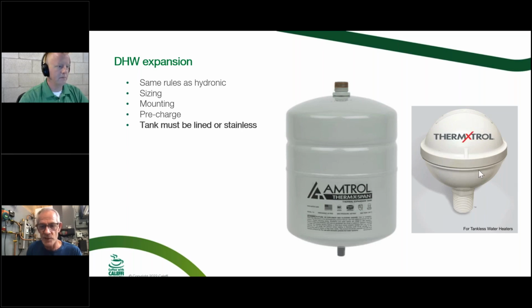And one of the pre-submitted questions: if you have a bank of these tankless water heaters, you still have to be able to accept the expansion of that. And at the last AHR show, I saw, I think it was a Rinnai brand, hanging on the side of a 50-gallon tank. So a tankless water heater on a 50-gallon tank, you kind of have a tank water heater, so you've got to size your expansion for that whole thing, not just for that little tankless water heater capacity. So anything else? Yeah, the other thing I'll bring up too is, a lot of guys, expansion tanks might be code in your area for the contractors and for the engineers.